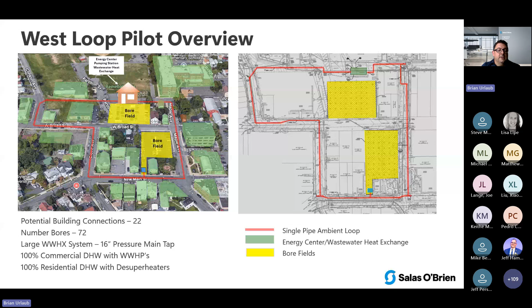If we parallel that off with the bore field and the sewage heat recovery in that location, we can serve that school differently than just keeping it as a typical connection point like every other building off the loop, because the large load really drives the total flow of the ambient system. You can't have less flow on the ambient than you do on one particular takeoff. So on a couple of projects we've taken that particular building and put it in parallel, feeding it from that energy source to help reduce the cost and size of the rest of the system. We want schools and large buildings on these systems, but if you have one large building and a bunch of small buildings, that large building is going to be the driver, and it's also going to drive your costs for the whole system. So you have to figure out a different way to do that.